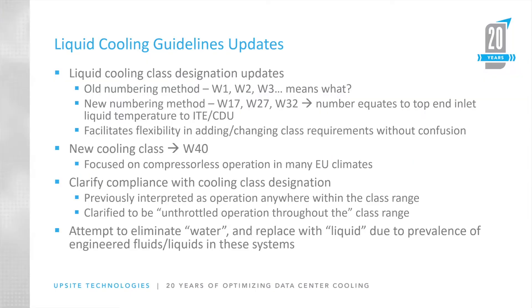The liquid cooling section went through a significant update. The primary change is the designations — the numbering method. The original classes were W1, W2, W3, which weren't very intuitive. We changed them to W17, W27, and W32. What this means is that if you're talking W27, the water supply to either the CDU or the IT equipment has a maximum of 27 degrees centigrade; W32 accordingly has a maximum of 32 degrees centigrade.